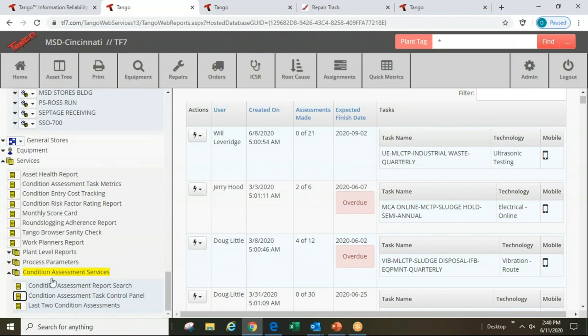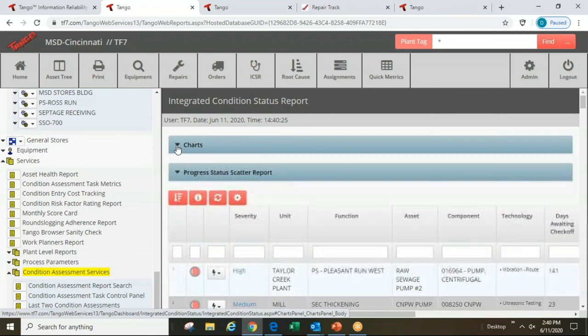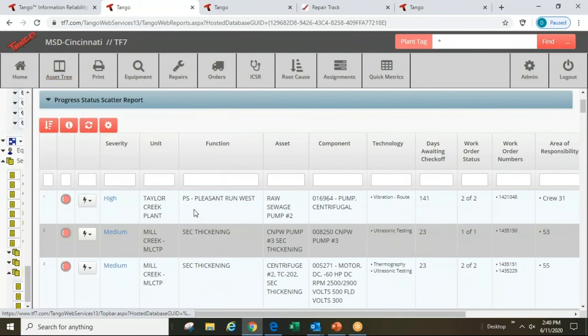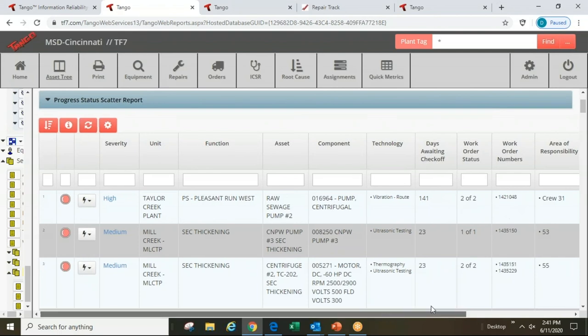Once tasks are completed, we move to best practice number six — having all information in an integrated dashboard. Looking at the whole plant, I can see a high severity issue on a centrifugal pump — raw sewage pump number two — coming from route vibration. It's been out there for nearly half a year, and we do have two work orders open on this.